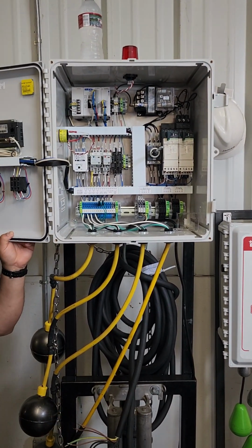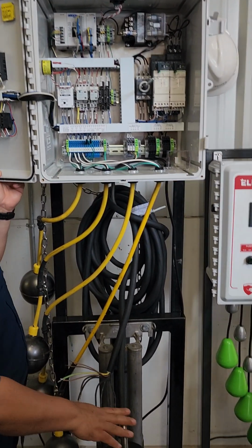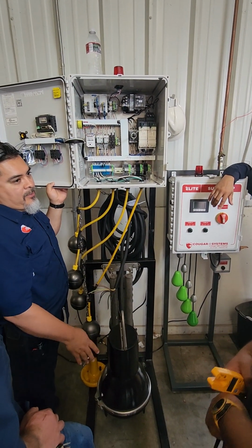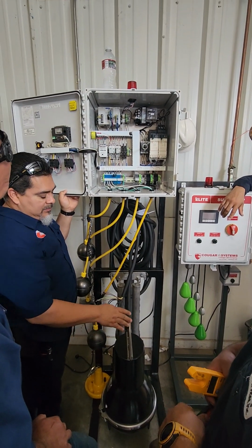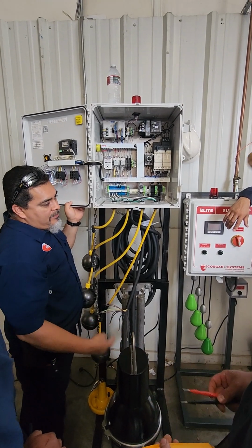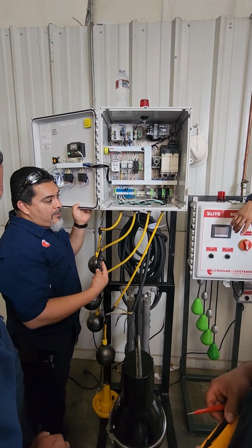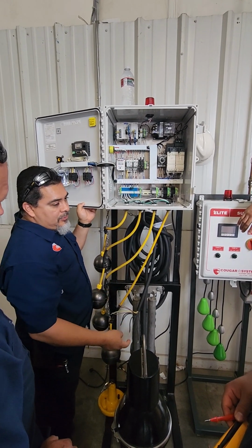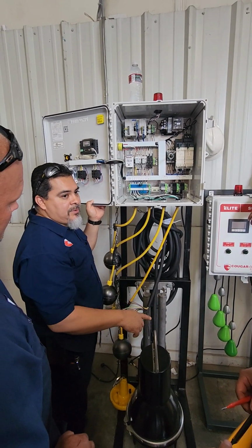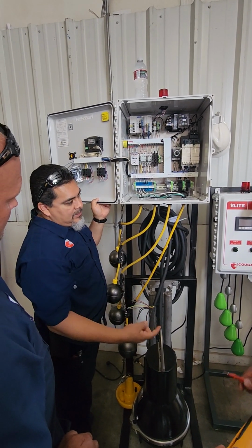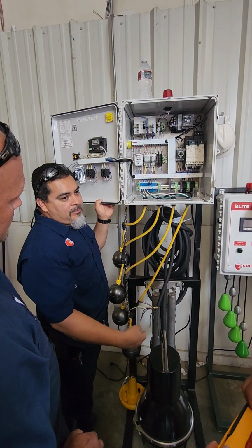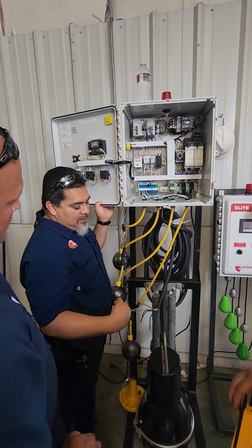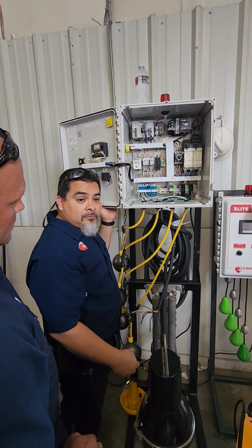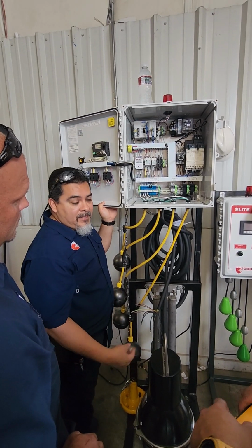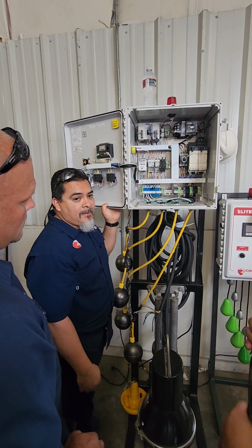Pumps. When you install pumps, if you do a small horsepower pump, say 2 horsepower or below, there's a high possibility that when you turn it on, it will still pump, even in reverse. So you have to make sure you always check your rotation first, because it could be running backwards, and before you know it, the impeller falls off. The impeller falls off? Yes. If you run in reverse for a long time.